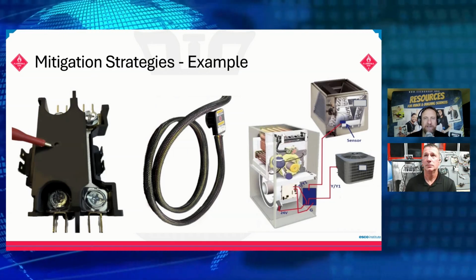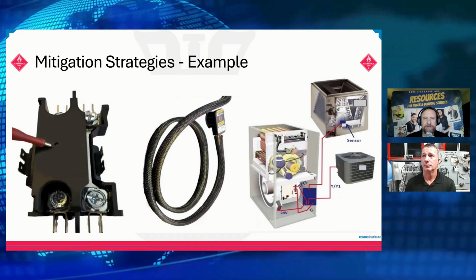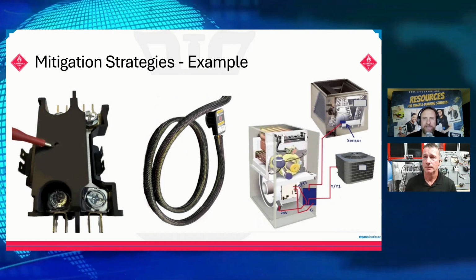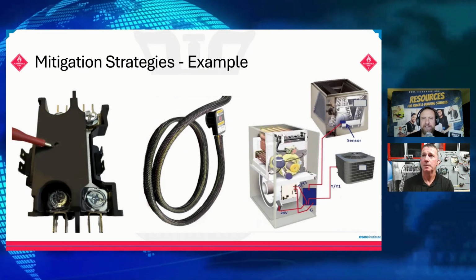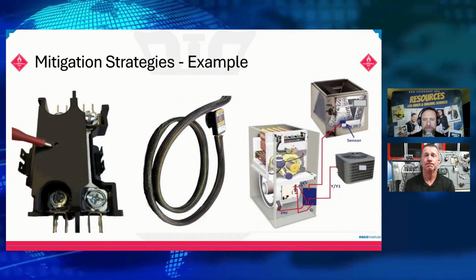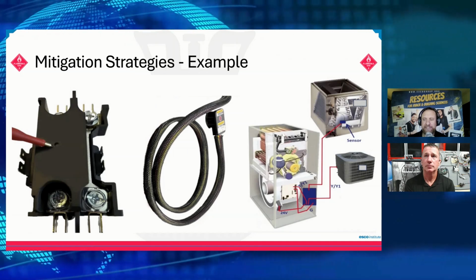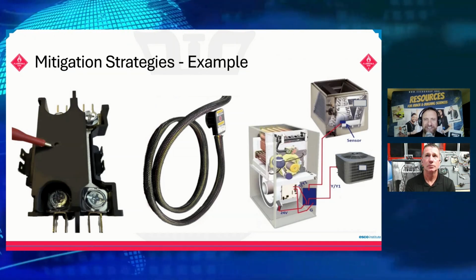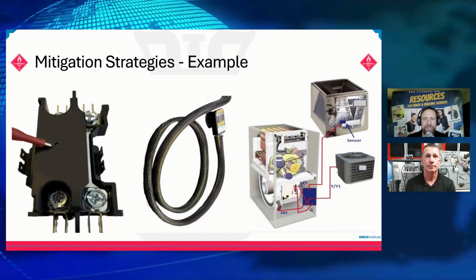And if we think about it being a gas furnace or an oil furnace, if we end that W call, if it's a gas furnace, we immediately lose our gas valve, losing our fuel for combustion. And if it's an oil furnace, the same thing, we immediately shut off our fuel. We shut all that down, and we're still going to run the fan. So the mitigation for the oil furnace is still in play, just like it would be a gas furnace. We end that W call, and we let the furnace take care of itself. So even if we don't have an oil furnace that has the controls built into it, if we have that mitigation board, we add that in, and it does the same solution.